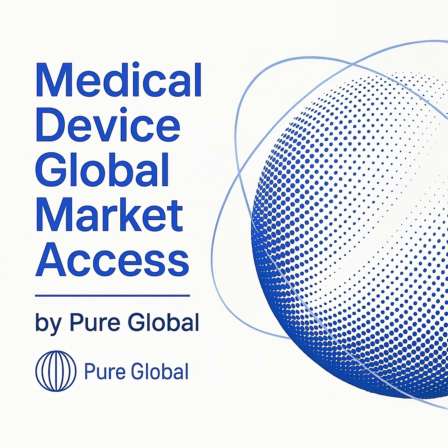All investigational devices must be properly labeled with the statement, "Caution, investigational device, limited by federal or United States law to investigational use." The sponsor of the study is responsible for making the initial risk determination, but the IRB ultimately makes its own assessment. If the IRB disagrees with the sponsor's NSR assessment and determines the study involves significant risk, it will inform the sponsor, who must then submit an IDE application to the FDA.